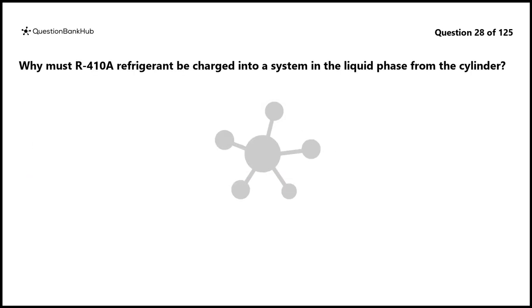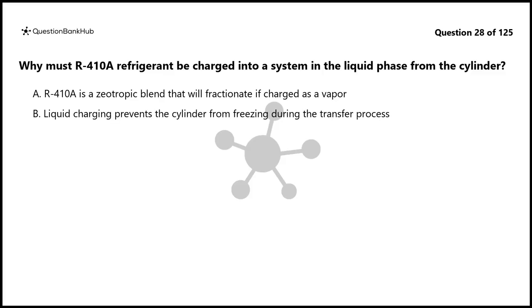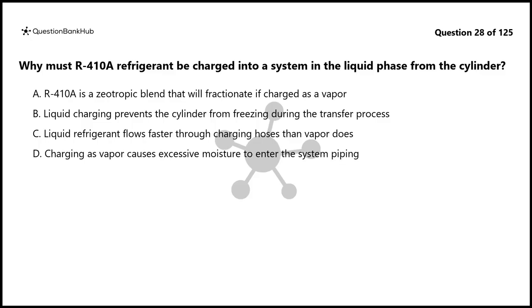Question 28. Why must R410A refrigerant be charged into a system in the liquid phase from the cylinder? A. R410A is a zeotropic blend that will fractionate if charged as a vapor. B. Liquid charging prevents the cylinder from freezing during the transfer process. C. Liquid refrigerant flows faster through charging hoses than vapor does. D. Charging as vapor causes excessive moisture to enter the system piping.